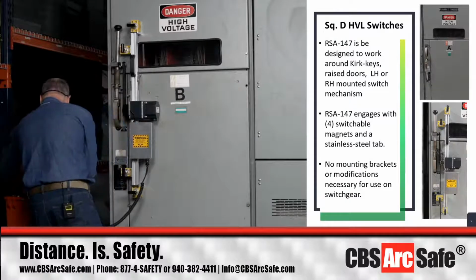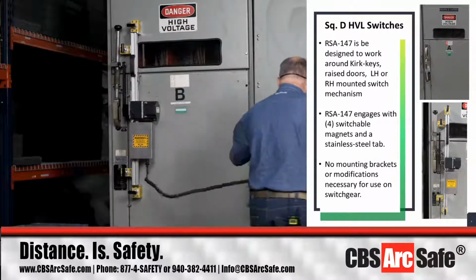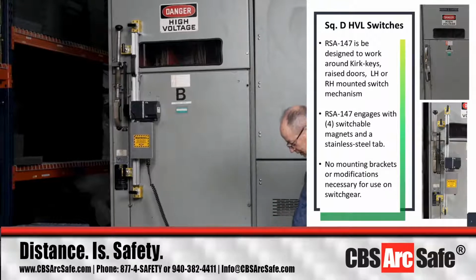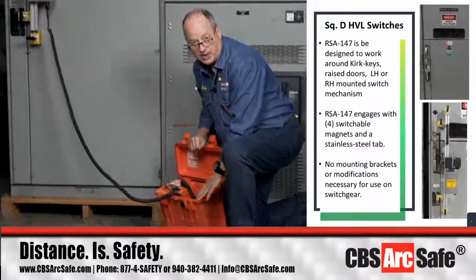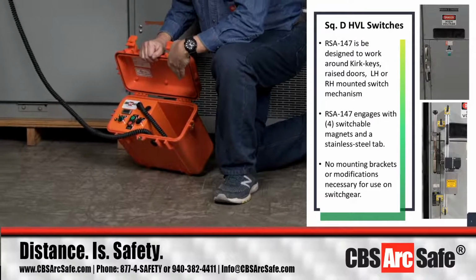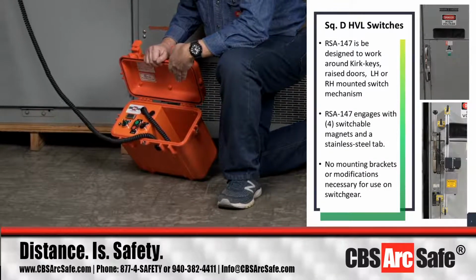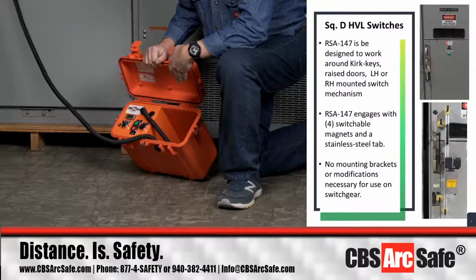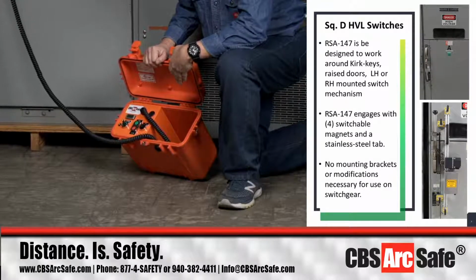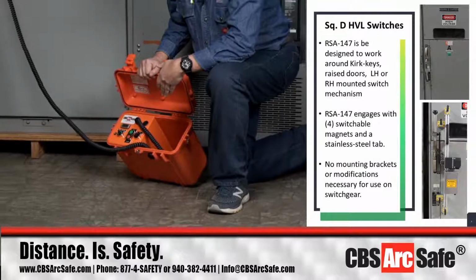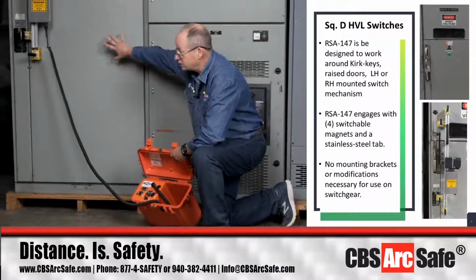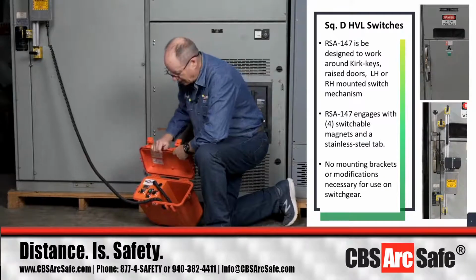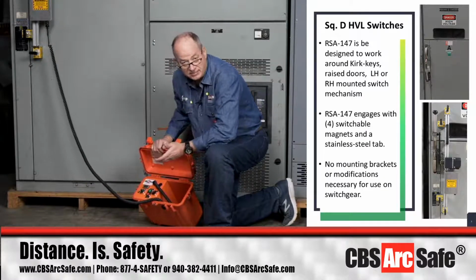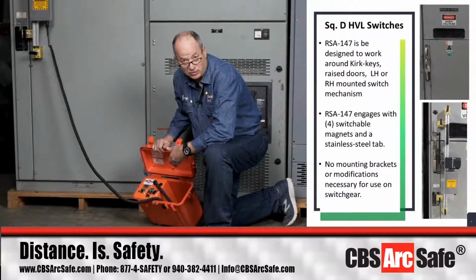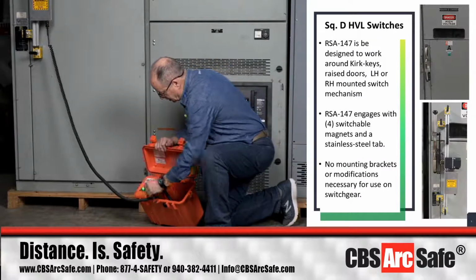The standard RSO1, while I'm doing this from right here, remember, I can get this up to 30 feet, about 10 meters away. So you want to get this outside of the arc flash hazard boundary before we turn it on and actuate it. That's what we would normally tell you, the customer, to do: look at your sticker on the switchgear, step out of the boundary and operate it there. If you have high boundaries, we also make these with radio remotes so that you can operate them up to 100 meters away. So we'll turn our power switch on.